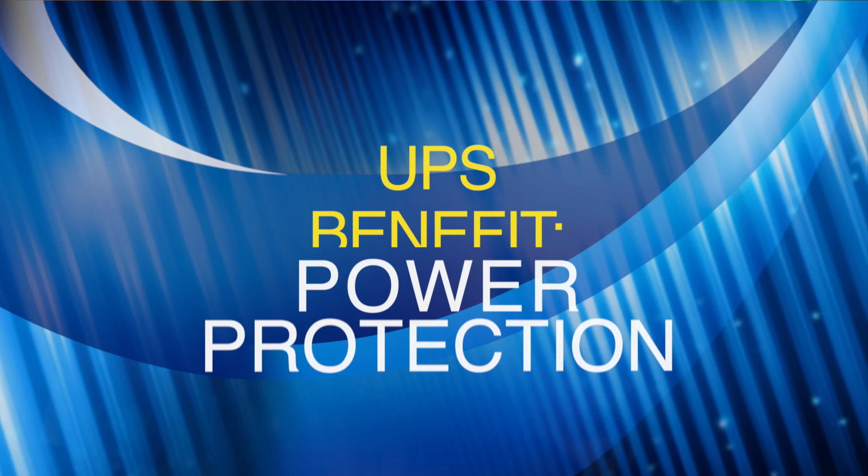Power protection. With a UPS, you get protection from various power-related issues such as blackouts, which are the complete loss of power, brownouts, which are reduced voltage, power sags, which are short-duration voltage drops, and voltage spikes where the voltage goes too high, and surges, which are longer-duration high-voltage events. These disturbances can cause hardware damage or loss of data, or both.